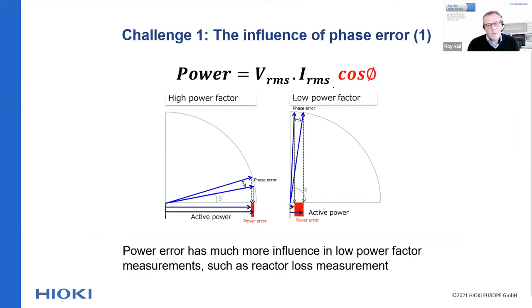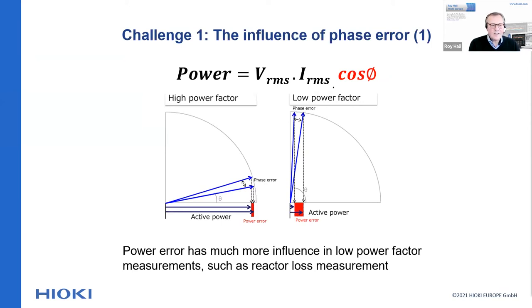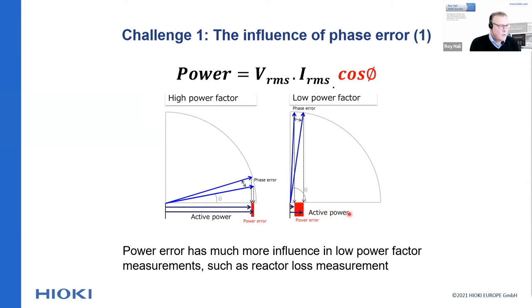The first challenge we face is the interference of phase error. Looking at two phase diagrams: on the left side you see the vector diagram of a device with a high power factor — for instance a power resistor — where the influence of the power error (the red area) is very small compared to the measured active power. However, on the right-hand side, the power error is very large compared to the measured active power. Therefore, as soon as you measure at low power factors, it's extremely important to compensate for the phase error.